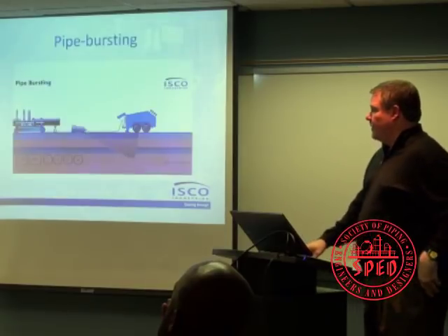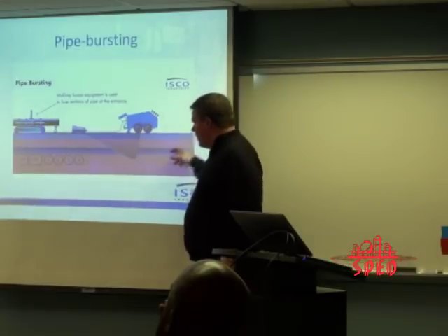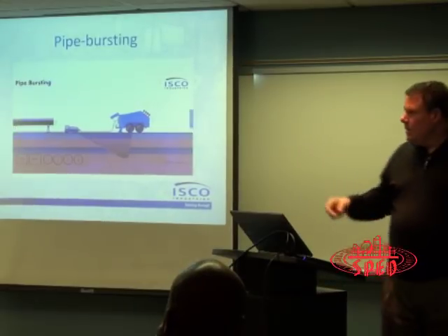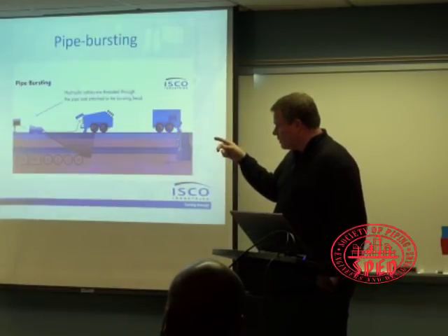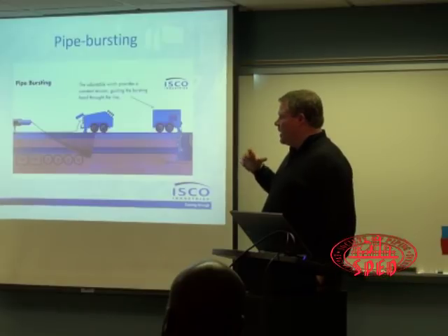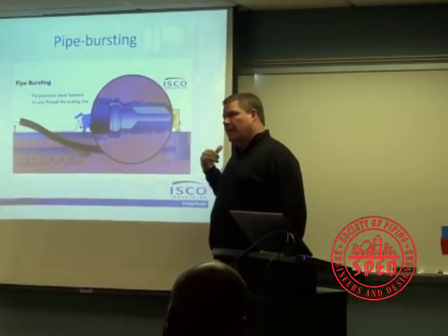We can go right down the street if you want to. Next one is called pipe bursting. You look at your current line, you say, I have a community that's growing, this 8-inch line's not going to work for me anymore, I need to go to a 12-inch. Again, it looks just like slip line. The difference is they put a pneumatic hammering head in the front of that polyethylene. As they're winching in the 8-inch pipe, they're expanding and contracting on that, and there's blades that will cut that existing pipe, break it apart, and pull the polyethylene through.